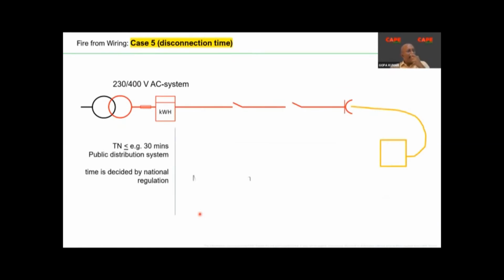When it comes to the disconnection time, starting from the transformer up to the final equipment, the maximum disconnection times are very well established in the standard. Your design, as Suresh sir told, most of the electrical safety things you are supposed to take care of during the design and implementation, or during design and erection, not after that, because once you have erected your installation, it is very difficult to establish. So disconnection times are very important.